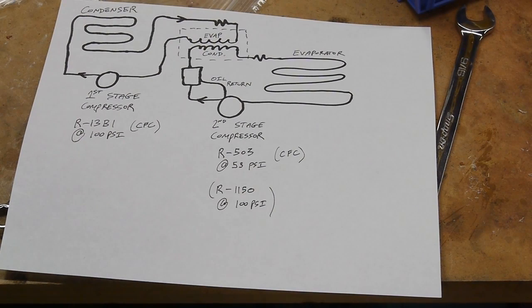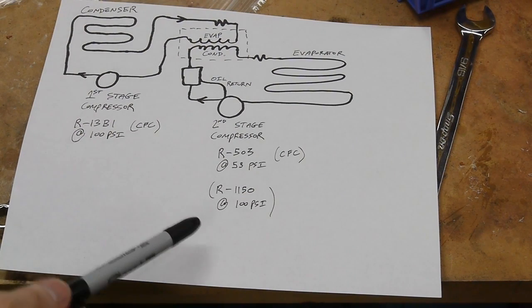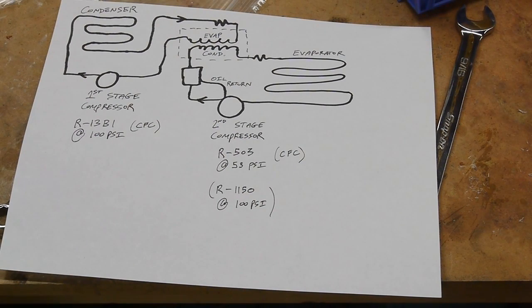I should also note that in most refrigeration systems the amount of refrigerant in the system is usually stated in terms of mass. In systems like car A/C with R134A, you can't measure the amount just by checking the pressure because there's an equilibrium between gas and liquid. However, in these low temperature systems the refrigerant is always a gas at ambient temperatures and pressures within the system, so if we know the ambient temperature we can use a gauge to figure out how much substance is in the system since it's linearly related.